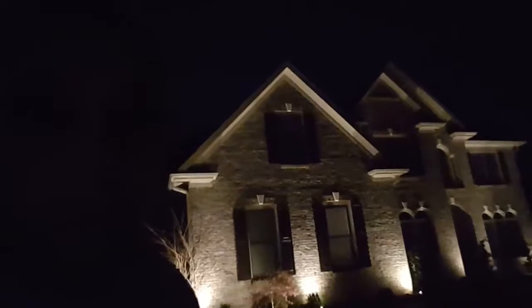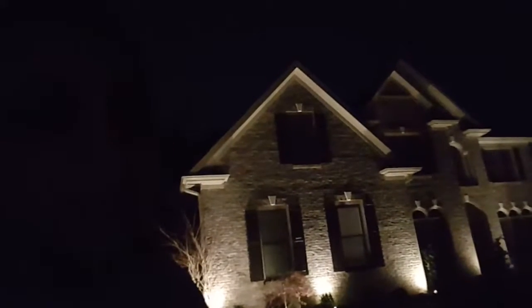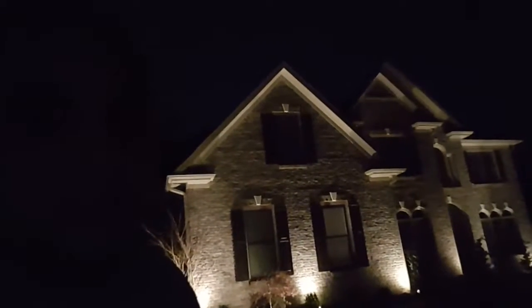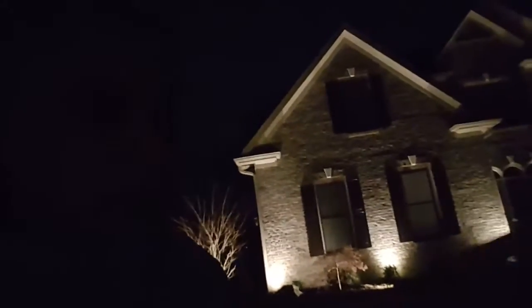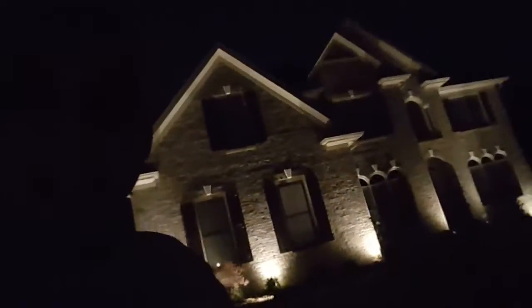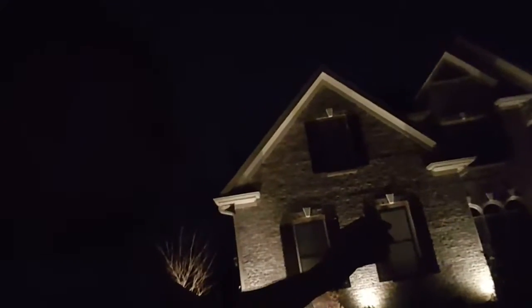If this were an older halogen-style system, I wouldn't necessarily be able to do that. The ability to do that comes with using LED fixtures. The internal circuits on LED fixtures allow them to operate in a wider range of output voltage, so an LED fixture won't burn out, will still last, will run cool, and you won't get variations in light between the first and last fixture, especially on these shorter runs.